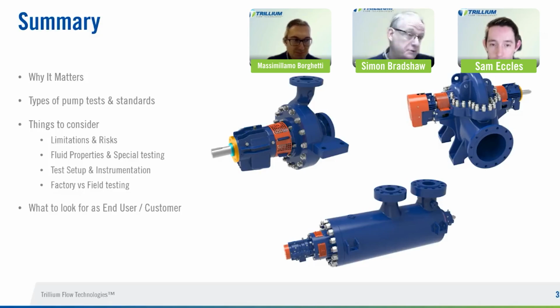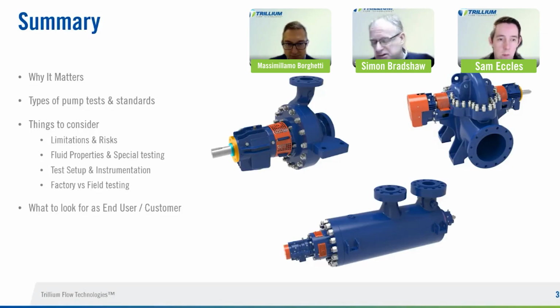I should say also the hydro test is mandatory as well. In terms of HI 14.6, once you're outside of that, if you're going to some other industrial standard that governs ANSI or ISO pumps, they do mandate certain testing. It is very, very limited in my experience. So generally, the safe answer would be that you would need to specify it.